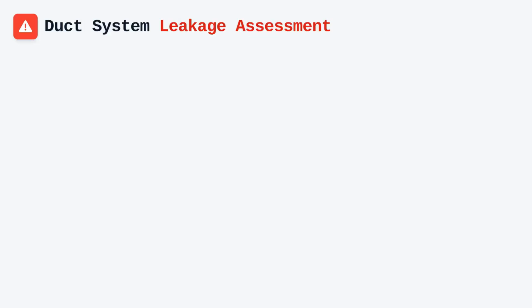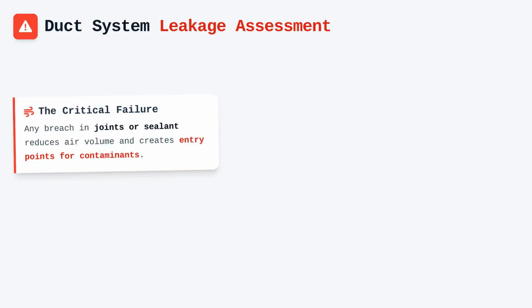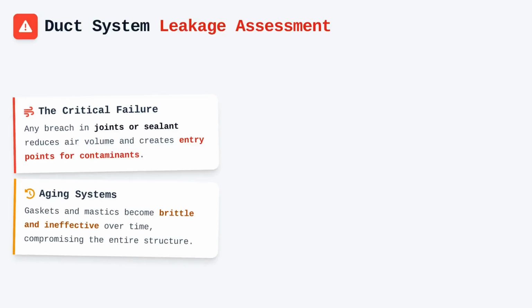Leakage is perhaps the most significant functional failure you will encounter when assessing a duct system for cleaning. Any breach in a duct joint, whether from degradation of sealant or physical impact, reduces the effective volume of air handled by the equipment and serves as an entry point for contaminants. When working on older systems, you will often find that gaskets and mastics have become brittle and ineffective, which complicates the setup of your negative air containment.